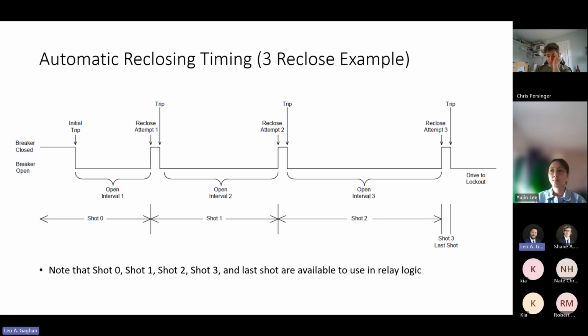So we'll start in a completely normal situation, right? The breaker is closed, load is flowing, everyone's happy. Well, we get that initial trip right here at time, we'll just say, time X, whatever it is. So when we get this initial trip, the breaker is going to open, right? Come down here and it opens. So let's say that's going to be open for, let's just say 10 seconds. That 10 seconds is what we call an open interval. And that's a setting that we can define and say, okay, do we want it to be 10 seconds, 15? We can make that decision.